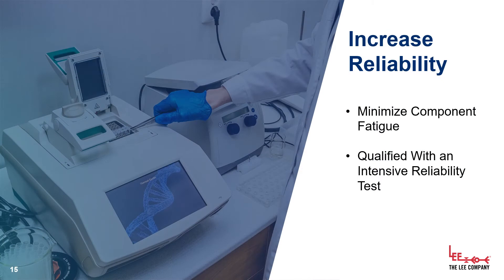Our next innovation was to improve the reliability of this valve to match the lifetime of the instruments it's designed into. We achieved our reliability goals through reduction of component fatigue. Our approach was to study the wear effects on previous generations of valves and formulate solutions to delay the wearing of the mechanism. After developing the design it was time to qualify — we subjected the valves to an intensive reliability test and have been able to qualify the valves to a significant number of cycles. We set a high standard for specifications because we understand just how expensive service calls are.